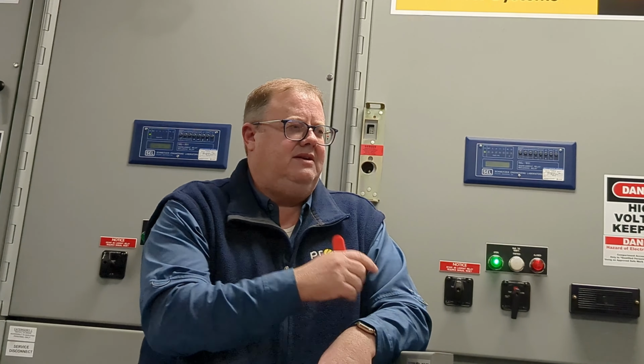Now on residential distribution, it's harder, right? Because you break off in your transformers and there's your circuits, you go different directions. But on a transmission line, I can get within 100 feet of where the fault is just by knowing what the fault current is, because I know the impedance of that line all the way down the transmission line.